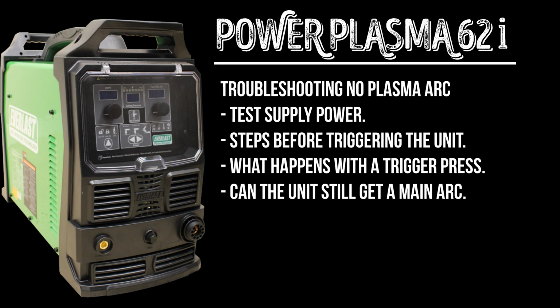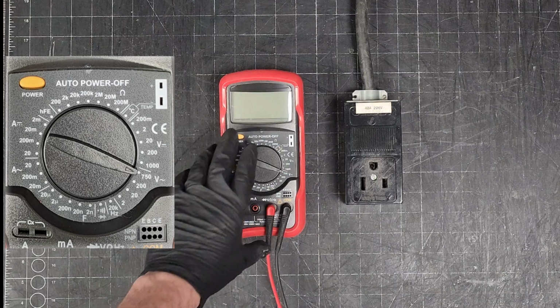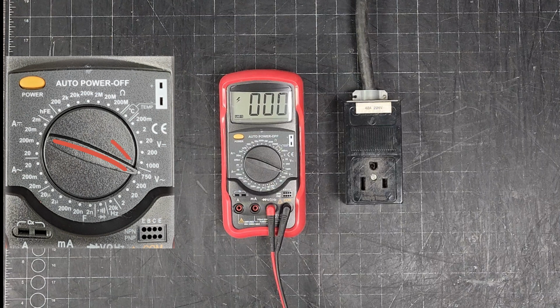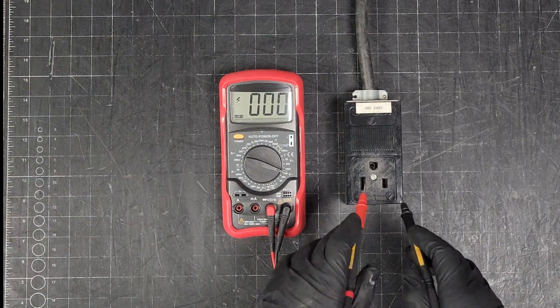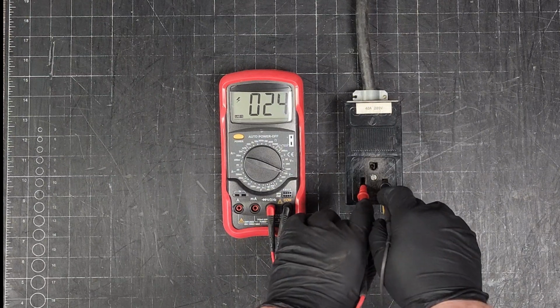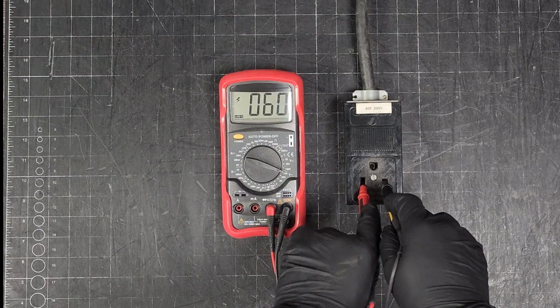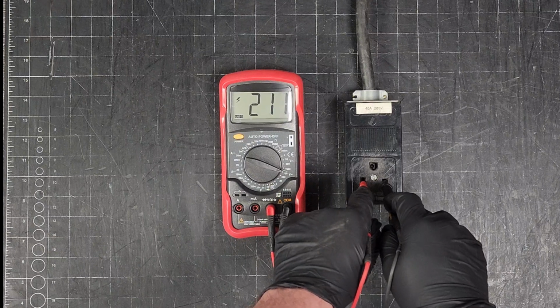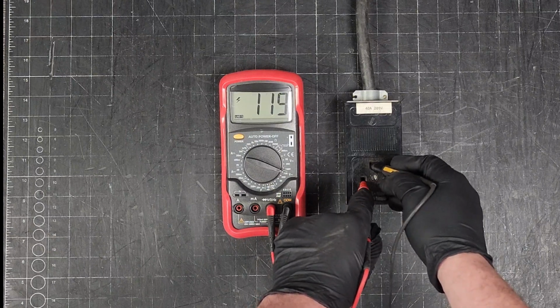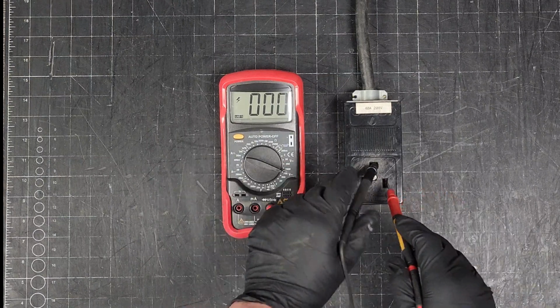In this video, we'll be covering the common questions and steps if you were to contact tech support with this described issue. We will start by confirming the correct voltage is supplied from your utility connection. Please set your voltmeter to measure 750 volts AC or greater. Then you can measure the voltage across the two straight blades, checking for 200 to 250 volts AC. Then you can test each straight blade to ground, checking for a similar 110 volt AC value.